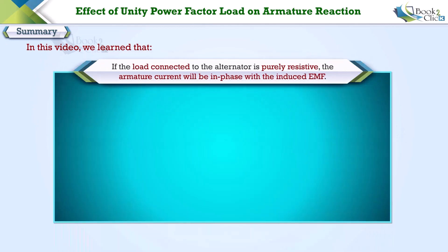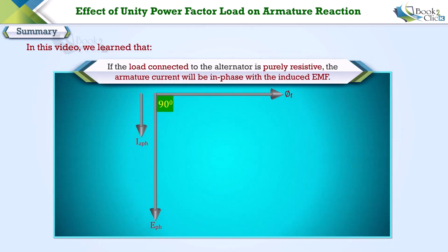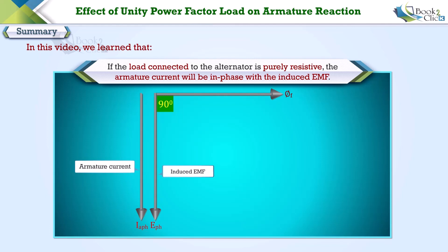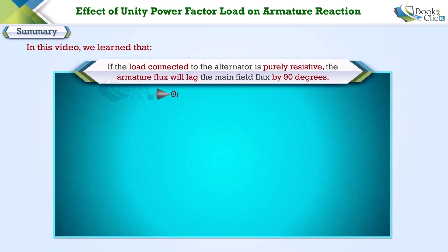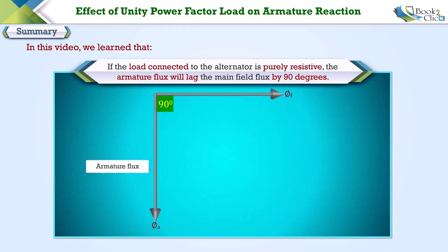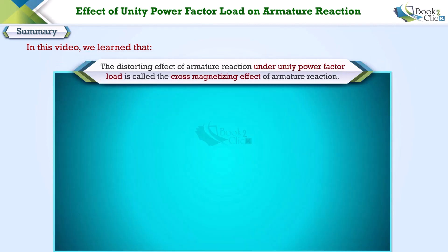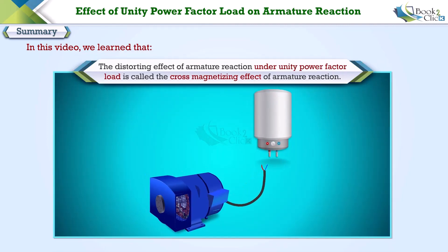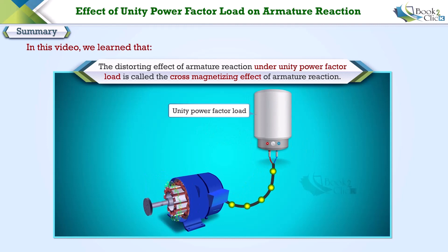If the load connected to the alternator is purely resistive, the armature current will be in phase with the induced EMF, and the armature flux will lag the main field flux by 90 degrees. The distorting effect of armature reaction under unity power factor load is called the cross-magnetizing effect of armature reaction.